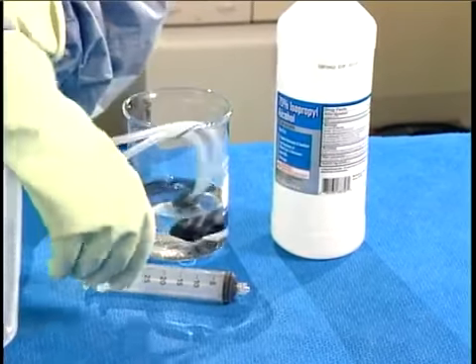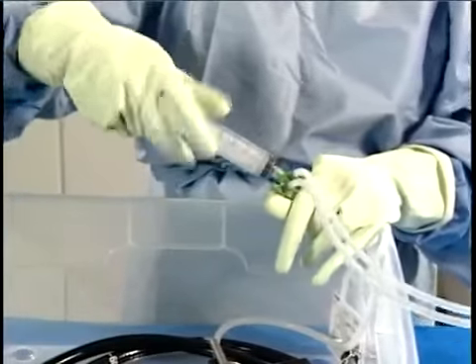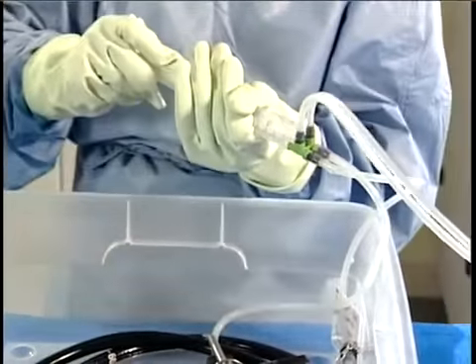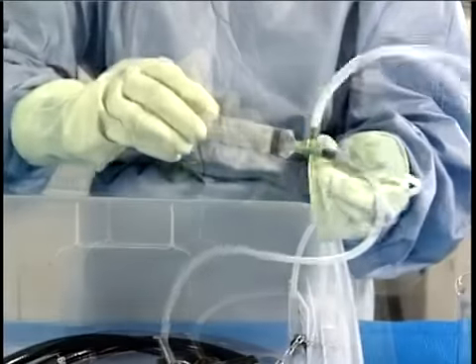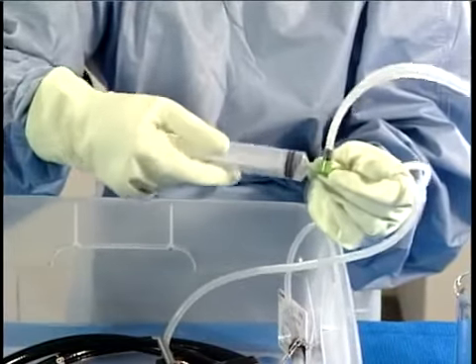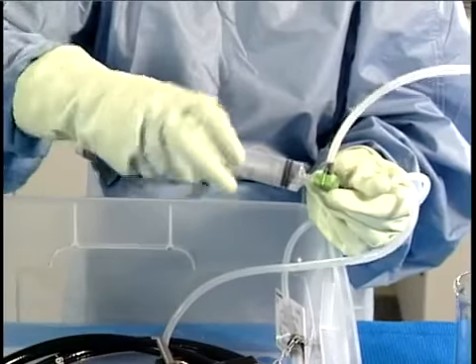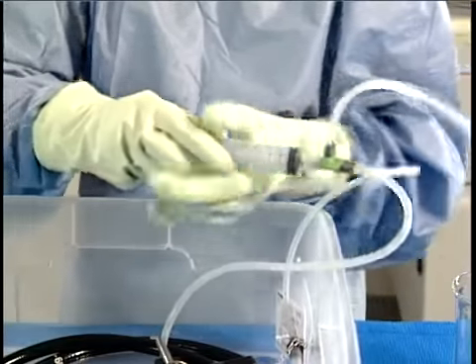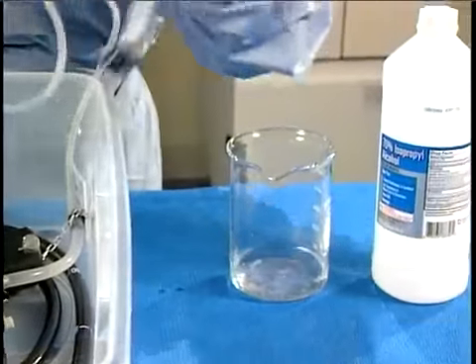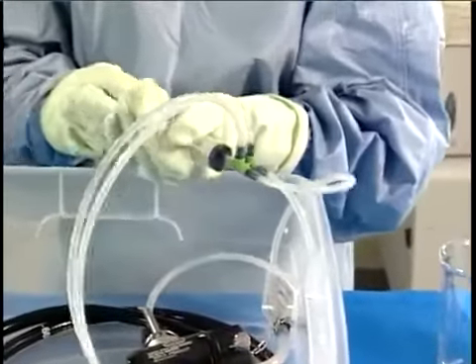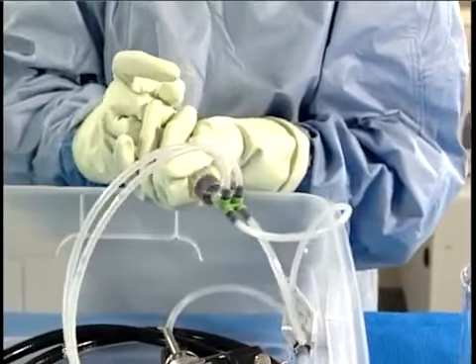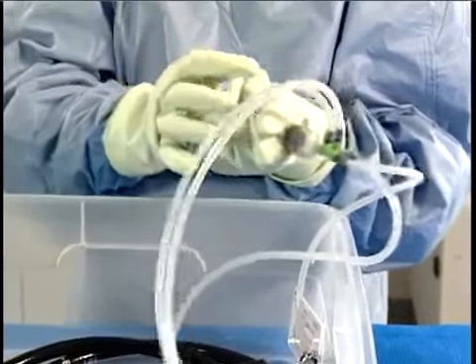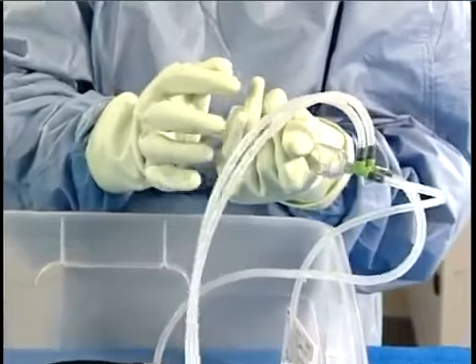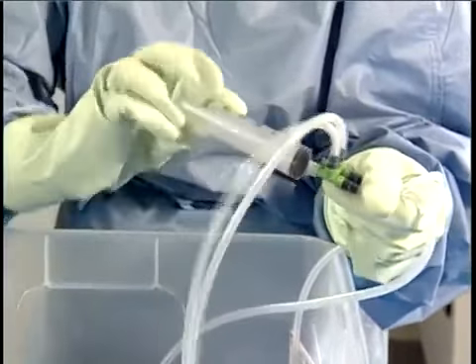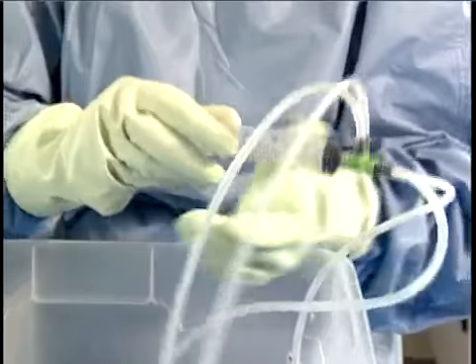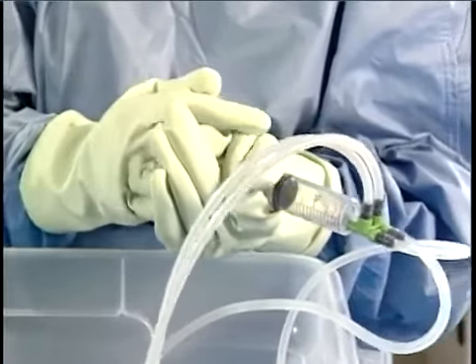Immerse the injection tube intake filter into the alcohol. Flush the air-water channel with 90 cc's of alcohol. Move the syringe to the suction port and flush the suction channel with 90 cc's of alcohol. Remove the injection tube's intake filter from the beaker. Flush the suction channel with 90 cc's of air. Move the syringe to the air-water channel port and flush with 90 cc's of air.